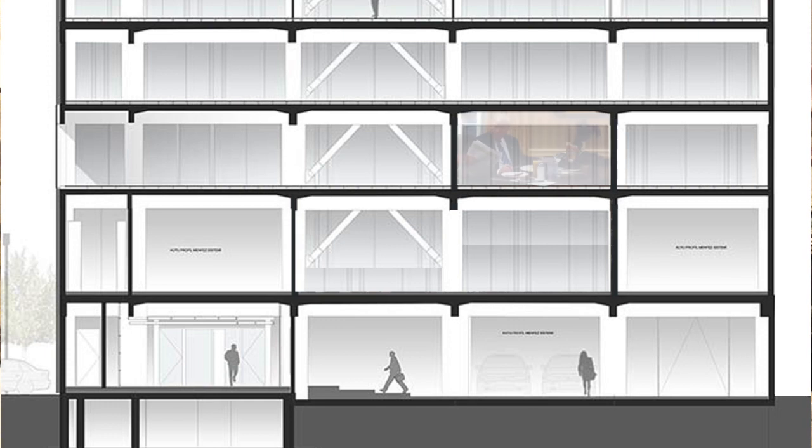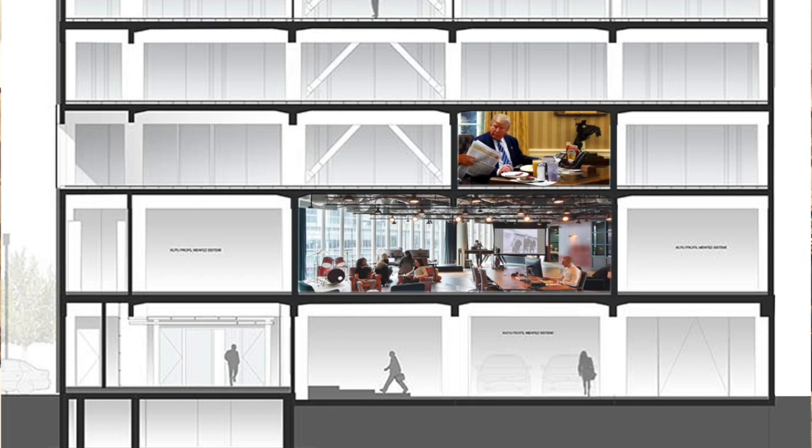Whether or not the opening between the mezzanine and the room it is in has been closed off according to code exceptions, the advantage of being in the room still applies. It is improper to ignore that part of the definition and just look at the requirements for maximum mezzanine area. If one used only the logic of maximum area, then any space, for example a third-floor office, could be considered a mezzanine of a larger second-floor space that happened to be below it, even if there were no logical connections between the two spaces, but only a vertical adjacency.